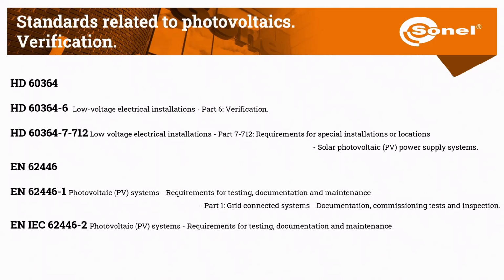installation, which is on-grid, where you have to make the measurements according to the standard 60364 when we talk about the AC measurement, and the standard 62446 when we talk about the DC side of the PV installation.